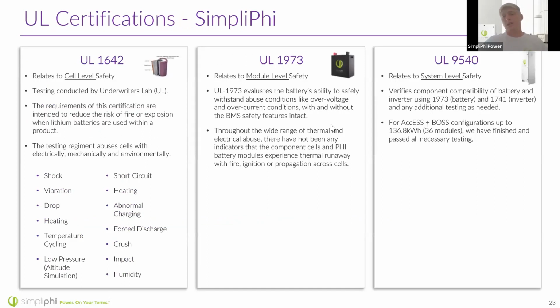There's been a whole bunch more safety testing done to our batteries as well, all the way from the cell level to an entire system level with batteries and inverter as a whole. So UL 1642 is a cell level test that's very similar to what you just heard about. We're talking about shock testing, drop, vibration, heating, temperature cycling, low pressure, short circuiting, and much more. Even crush testing, so just smashing that cell and making sure there's no fire. UL 1973 evaluates the battery as a whole and its ability to withstand abuse, I would say, and just generally harsh treatment of the battery, make sure there's no fire, make sure it still works.